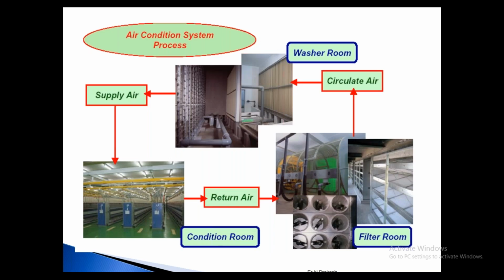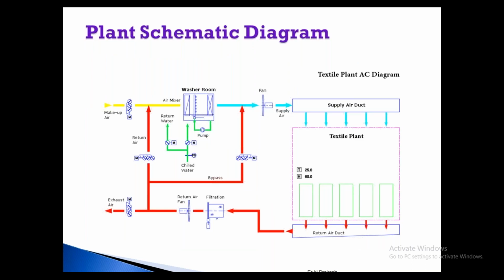So basically, what is the air conditioning humidification system in your textile plant? We have an air washer chamber, and air will be circulated through the air washer chamber. Water will be sprayed there, and the air and the water molecules will mix. It will atomize, and then only air will come out. Water will be eliminated as water droplets. Only air will come out. That air will have its temperature down. The temperature will get cooled, and humidity will increase after the eliminator. That air will come to the inside.